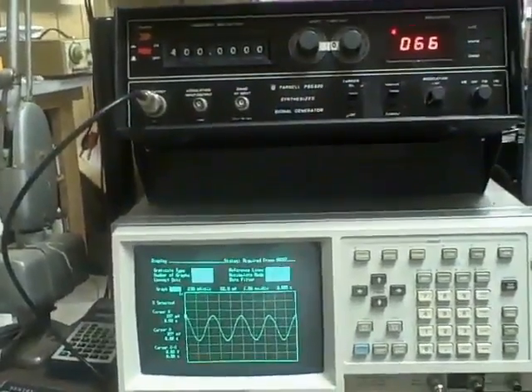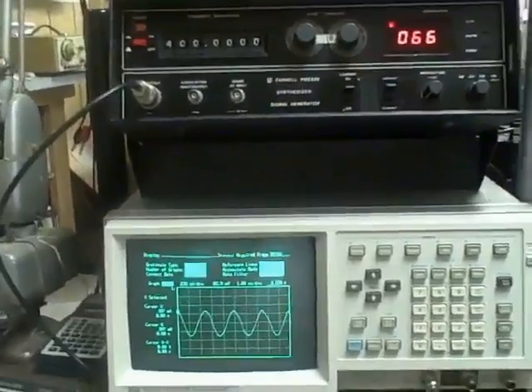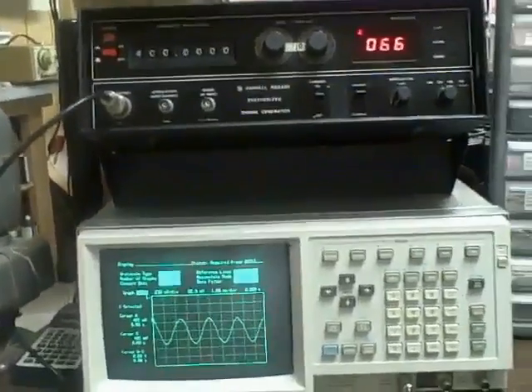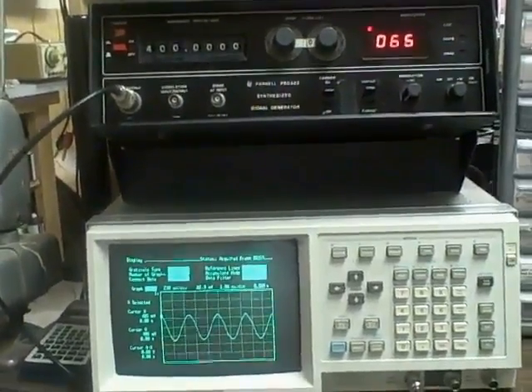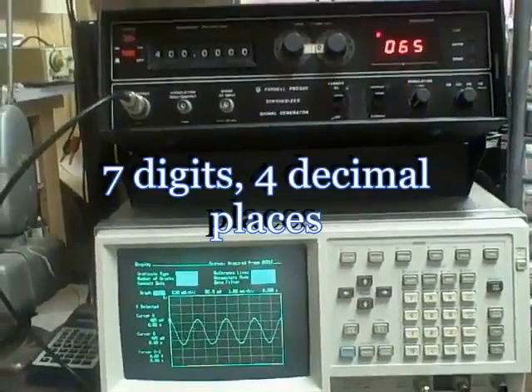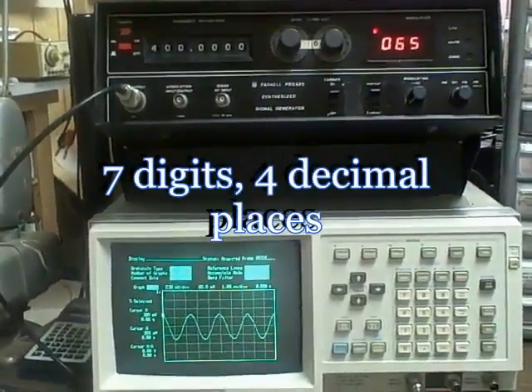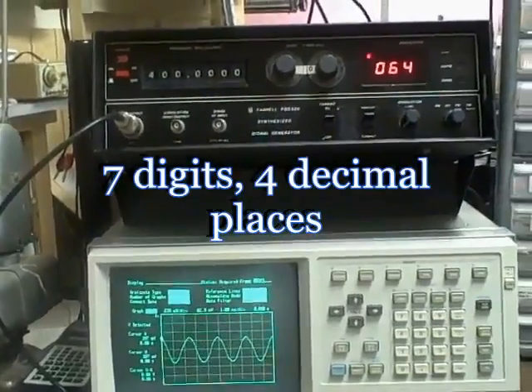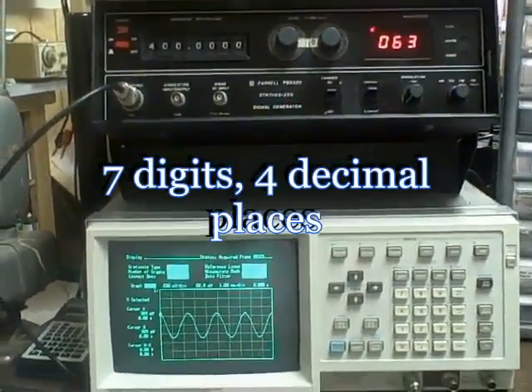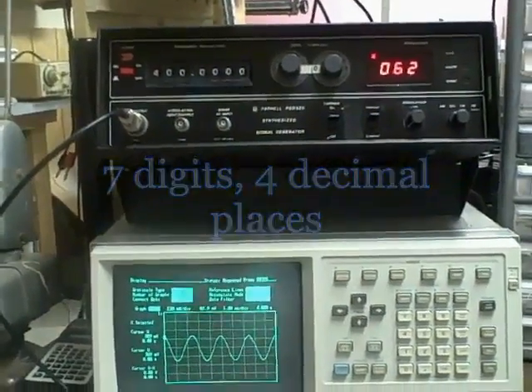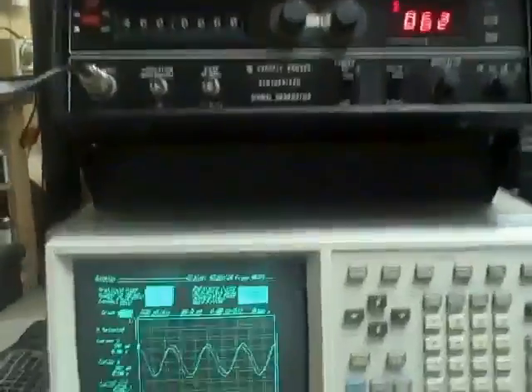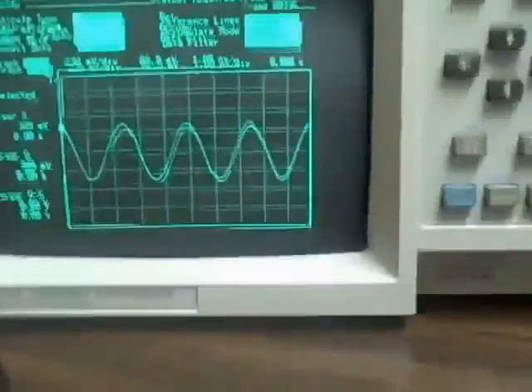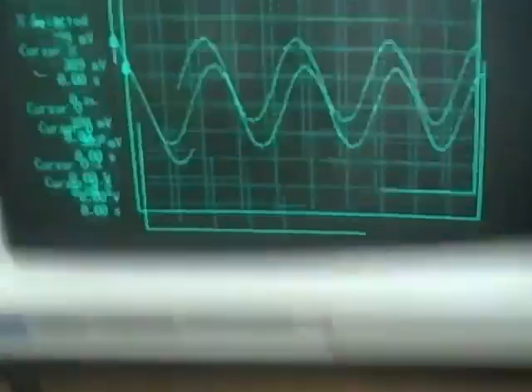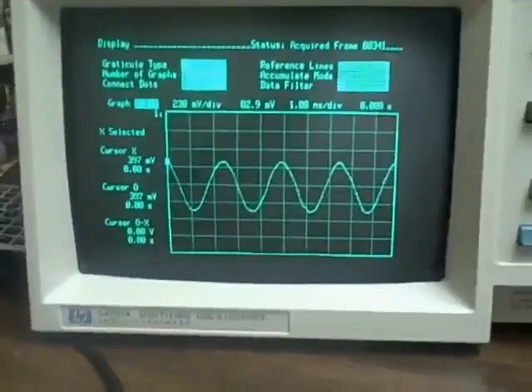Okay, what we're looking at here is a Farnell PSG520. It's a synthesized signal generator, and it's capable of producing 10 megahertz to 520 megahertz, and it does it to four decimal places, and does a very nice job of it. Right now, I'm using a Hewlett-Packard 54201A to display an output. The 201A is a 300 megahertz scope, it's the rating.